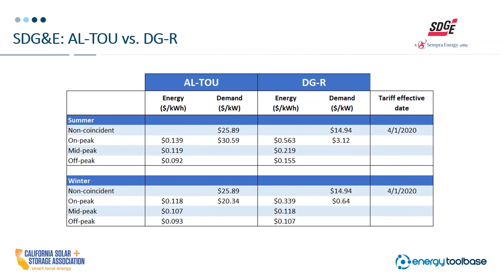So very high demand charges and what I would classify as pretty mild energy charges — in the summer anywhere between maybe about $0.09 and $0.14. When you rate switch and move your customer to the DGR rate post-solar or post-solar and storage, basically what happens is the demand charges go down really significantly. The trade-off is the energy charges go up. That's how the utility is recovering costs — instead of doing it through demand, they're doing it through energy. This is going to be really important to keep in mind when we look at case studies.